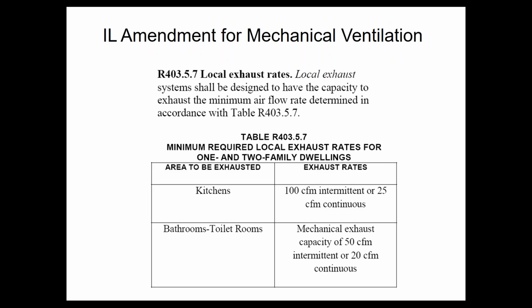Kitchens need either intermittent or continuous exhaust fans. That doesn't usually apply to HVAC, but some of you guys do that work. Same deal with bathrooms. They either need a fan on a switch doing 50 CFM, or they need a constant 20 CFM. Typically, if you're running an ERV, you're going to pull that 20 CFM.